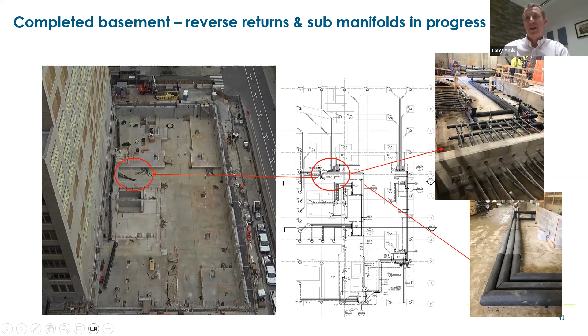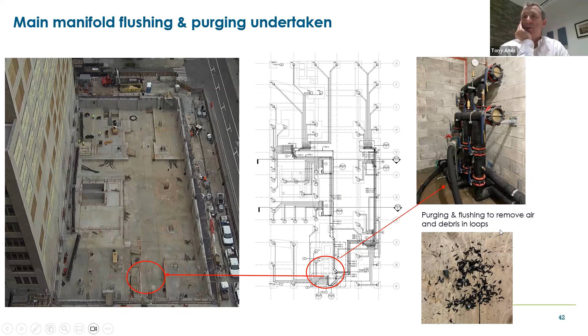What we see here is the final sub-manifold installed, and the next stage is to run up to the roof. But the key next stage for us was to flush out and purge the loops of any air. In that purging process, you can see the bits and pieces that have come out of the system - even a small stone, a piece of concrete aggregate, had got into the loops. Quite a lot of time is spent on this stage of works.